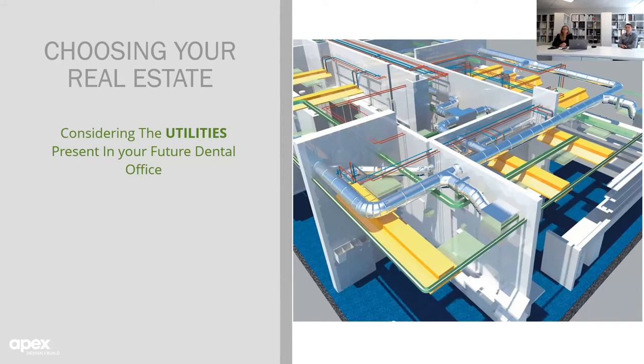Another system that we see is UV lighting within HVAC systems and within rooms. And we haven't been able to really recommend UV light systems due to the potential risk to staff. Now, I know that the IDPH here in Illinois did recommend a form of it recently. However, from our understanding, we've seen from hospital use that it's been known to discolor surfaces over time. They also deteriorate filters and plastic wire coatings and insulation and will break down the coil coatings within HVAC units. UV lights cannot reduce particulate or odors. Another issue is that the placement of these UV fixtures or fans would need to be optimized for the specific spaces, and the effectiveness has yet to be demonstrated within larger public spaces.